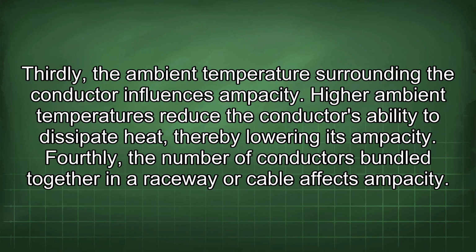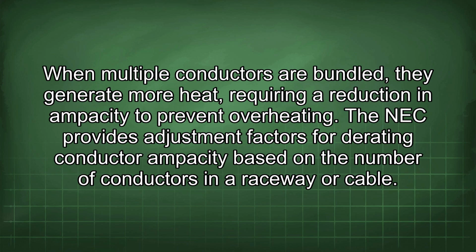Fourthly, the number of conductors bundled together in a raceway or cable affects ampacity. When multiple conductors are bundled, they generate more heat, requiring a reduction in ampacity to prevent overheating. The NEC provides adjustment factors for derating conductor ampacity based on the number of conductors in a raceway or cable.